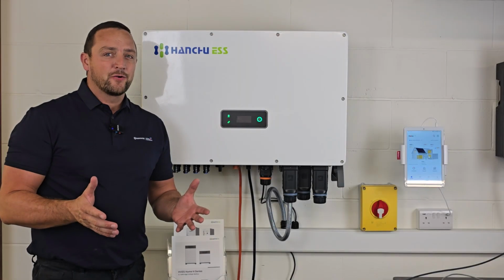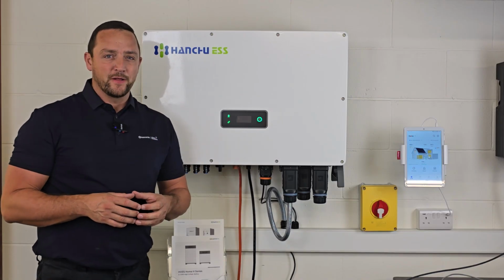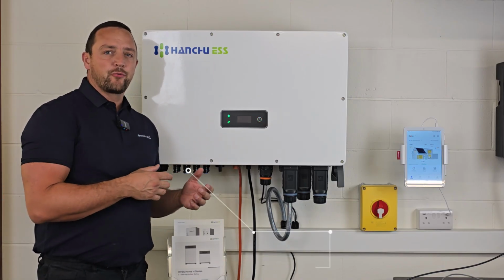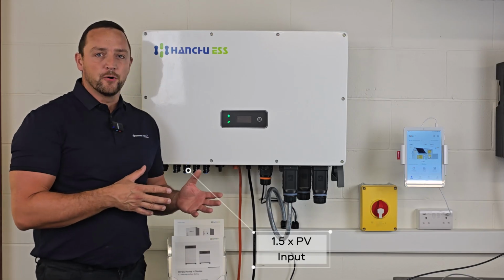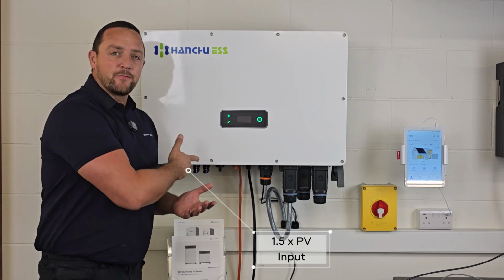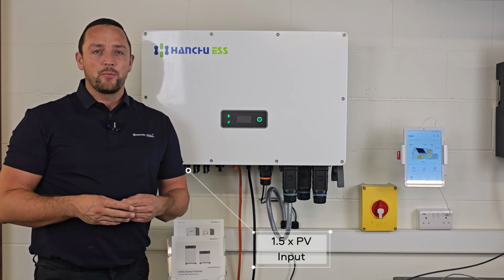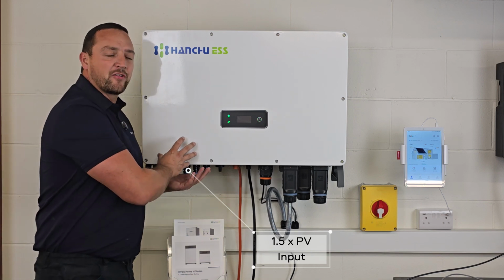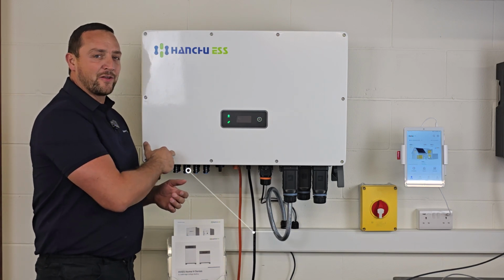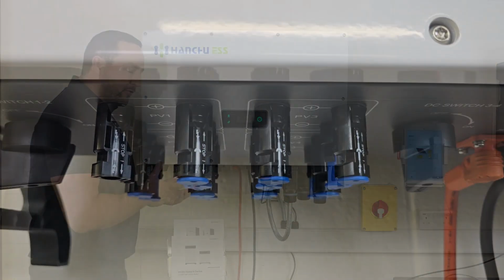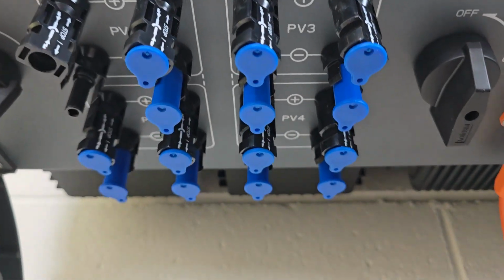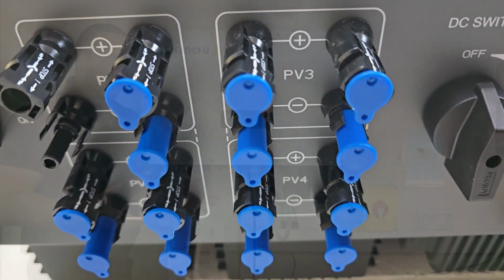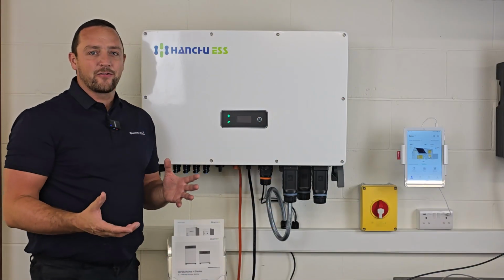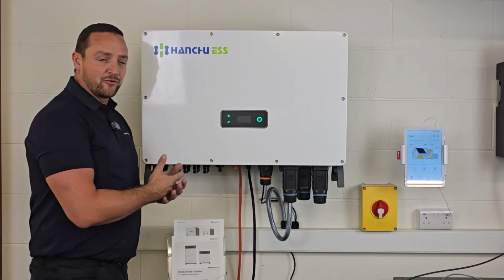So first of all, let's take a look at the solar input side of things. Each inverter supports up to 1.5 times solar input. So if we take the 50 kilowatt unit here, for example, we times that by 1.5, it means we can actually put 75 kilowatts in this single unit. It's designed with 4 MPPT trackers supporting up to 8 strings, which means now you can actually design a system to its maximum flexibility and efficiency.